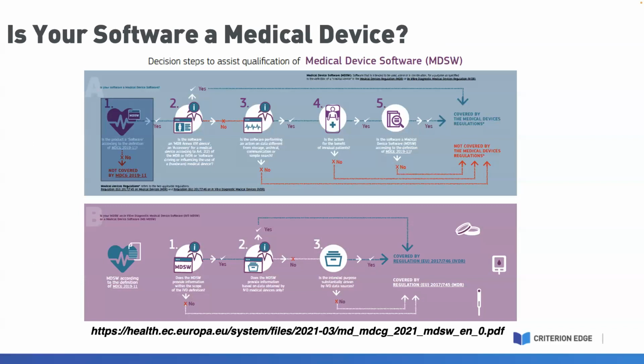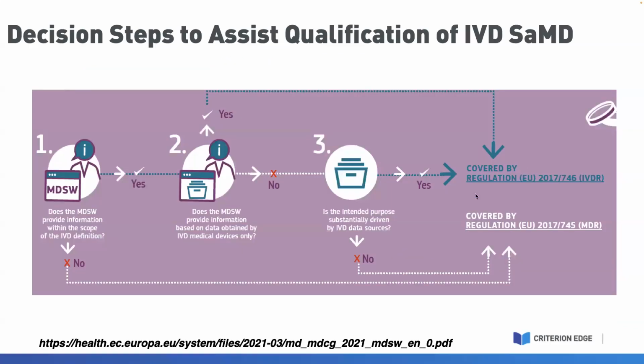So when you look at software, if its sole purpose is intended to drive or influence the hardware of medical devices without itself creating information for medical purpose, in those cases, it's not actually considered to be a medical device software, but it's still covered under this regulation as an accessory for a medical device or an IVD medical device, or as potentially an integral part or component of a medical device.